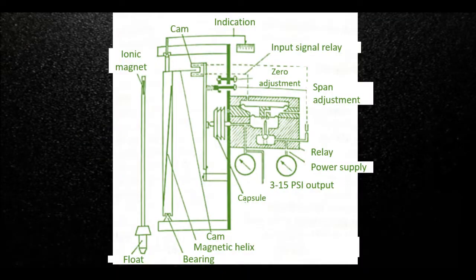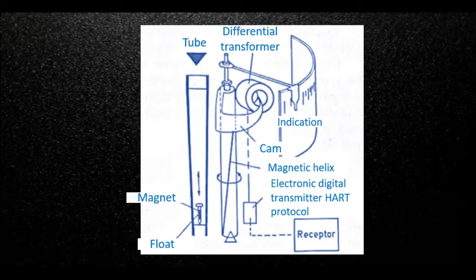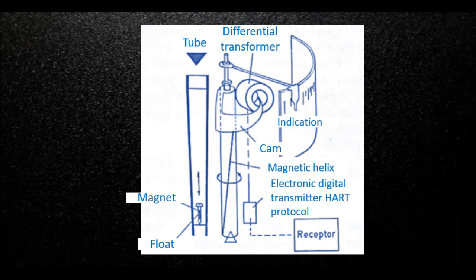The pneumatic ones consist of a cam that magnetically follows the movement of the float and is located between two pneumatic nozzles, which are part of a force balance transmitter. Electronic transmitters have transducers like potentiometric or impedance bridging. Both have a rod that magnetically follows the movement of the float inside the tube, and that drives a potentiometer or a moving core differential transformer, respectively.